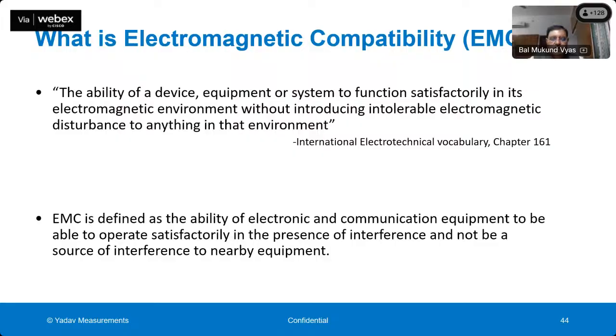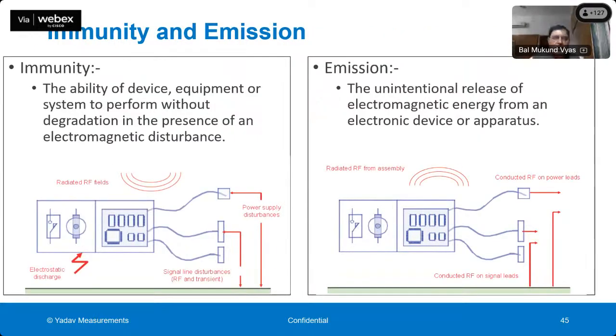One, it should function satisfactorily in the presence of various kinds of electromagnetic disturbances, and it should not cause disturbances to the others. So this one is called immunity and the other is called emission level. On the left-hand side, you can see immunity, which is the ability of a device, equipment or system to perform without degradation in the presence of electromagnetic disturbances. And on the right-hand side, you can see the emission limit, the unintentional release of electromagnetic energy from an electronic device or apparatus. So there are limits specified.